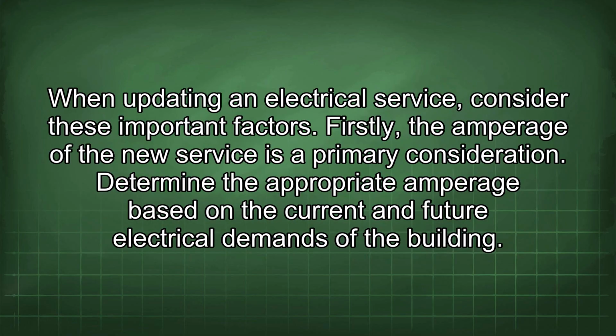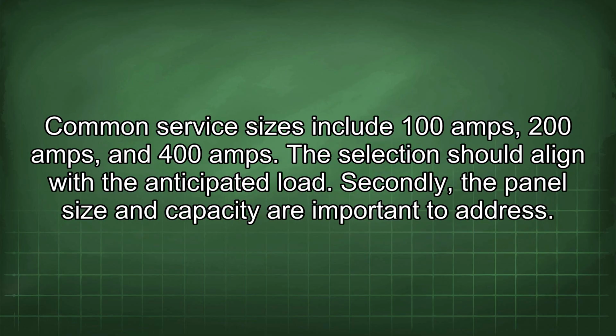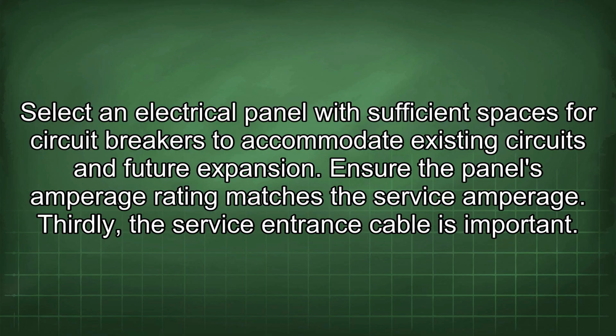When updating an electrical service, consider these important factors. Firstly, the amperage of the new service is a primary consideration. Determine the appropriate amperage based on the current and future electrical demands of the building. Common service sizes include 100 amps, 200 amps, and 400 amps. The selection should align with the anticipated load. Secondly, the panel size and capacity are important to address. Select an electrical panel with sufficient spaces for circuit breakers to accommodate existing circuits and future expansion. Ensure the panel's amperage rating matches the service amperage.